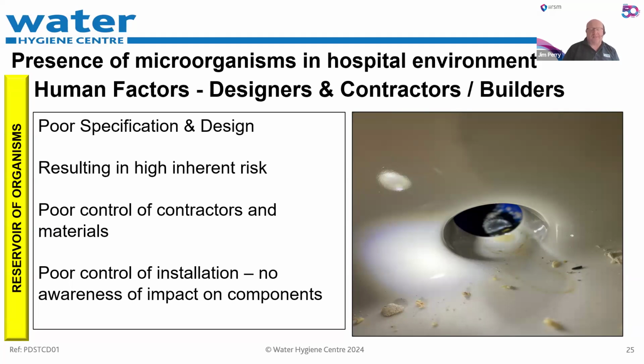Our domestic hot water systems not installed to the specific detail. We've got a recent example where the client had asked for all hot water returns to be within 300 mil of the outlet. 150 of these outlets did not comply with this. So the design wasn't being followed. We need people out in the field when these builds are happening, making sure that what's happening on site is as the design. We've got poor control of our contractors and materials, poor control of the installation, and no awareness of the impact on the components that can have an inherent risk at the end of the install.